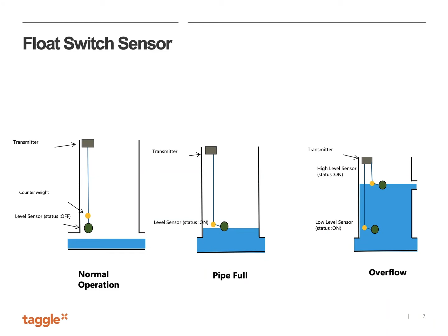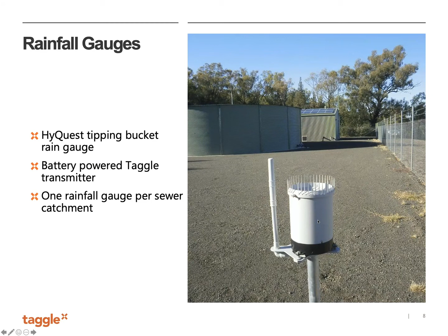So this is an example of a relatively low-cost rainfall gauge. It's a very high-quality gauge. This is in the same family as the one that the Bureau of Meteorology uses. And attached to the left-hand side of that is a Taggle transmitter. That unit stands alone. It doesn't require a communications cabinet, doesn't require any additional power supply. That's really just a pole concreted into the ground with a little bit of effort to make sure that the rainfall gauge is leveled. And if we put one of these in each catchment area aligning with the catchments of the sewer, we can now start to correlate rainfall in a catchment, which is indicated in this chart in blue, with the sewer level occurring in that catchment.